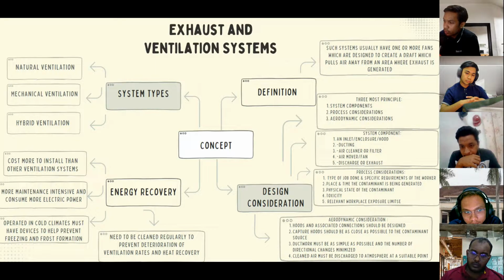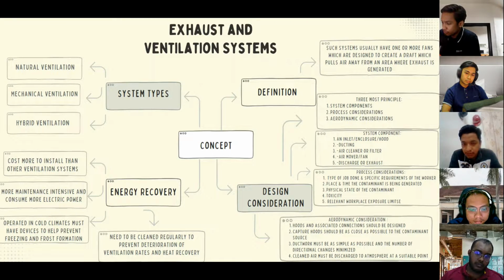And lastly, aerodynamic consideration. Hoods and associated connections should be designed well. Capture hoods should be as close as possible to the contaminant source. Next, ductwork must be as simple as possible and the number of directional changes kept to a minimum. And finally, clean air must be discharged to atmosphere at a suitable point. So these are the three main principles that are important in design consideration.